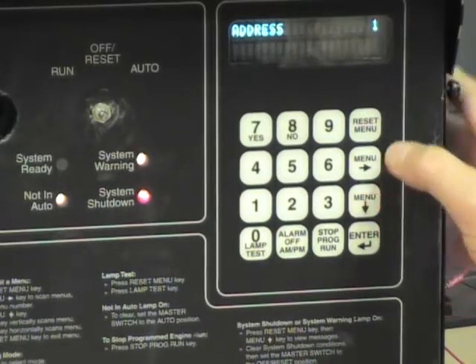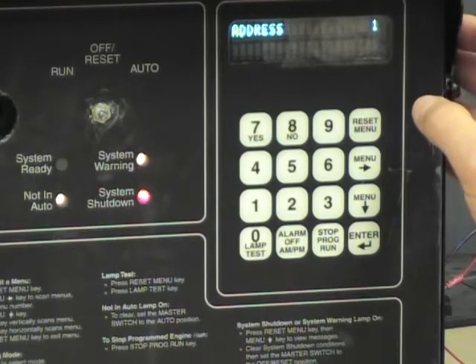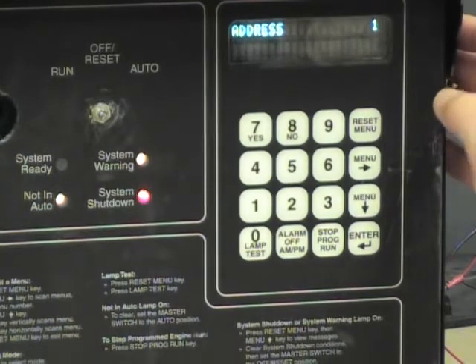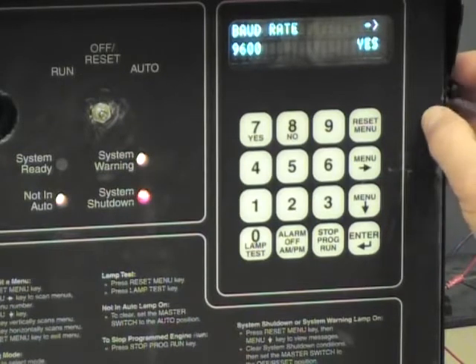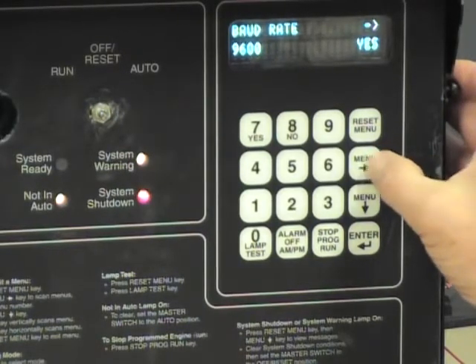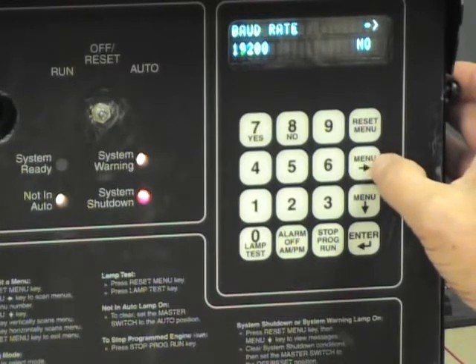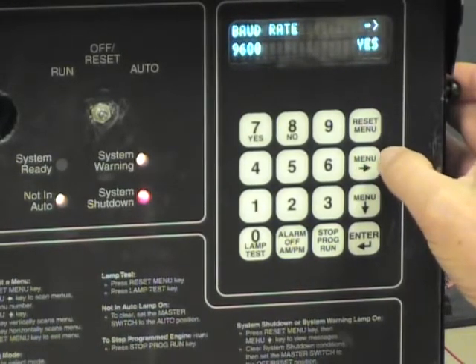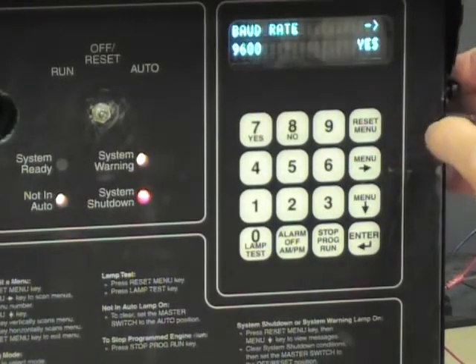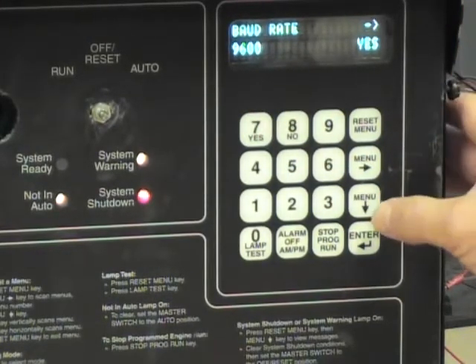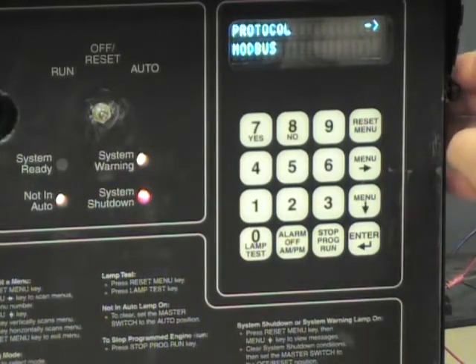Down one more time. The Modbus unit ID, or the address, is 1 — that's the default; we will leave it there. Down again, we come to baud rate. There are only two baud rate options: 9600 and 19200. We are going to choose 9600, so select it and press yes to make that change. Now we go down the menu one more time, and we're done with that configuration.